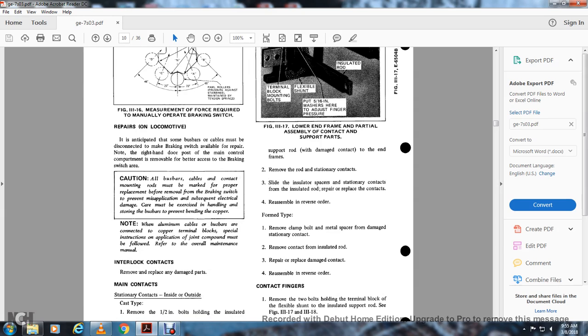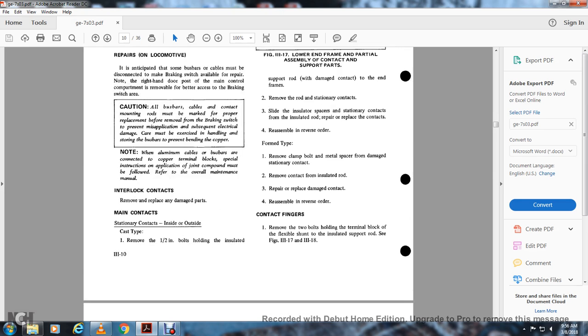The contact mounting rods must be marked with the proper replacement before the removal of the braking switch to prevent misapplication and subsequent electrical damage. Care must be exercised in handling the short bus, storing the bus bar to prevent injury with the copper. Note: when the aluminum cables and/or bus bars are connected with the copper terminals, special instructions to apply joint compound must be followed; refer to the overall maintenance manual.